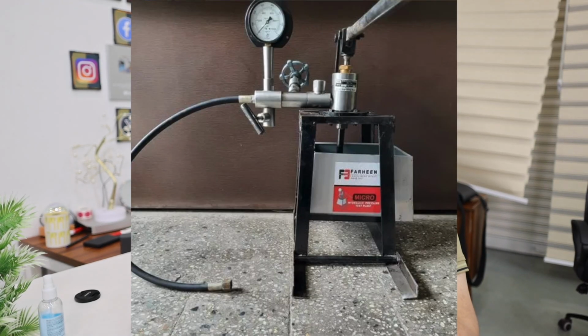Normally it depends upon the consultant requirement. 12 bar, 10 bar, or sometimes we do the testing at 24 bar also. It depends. And after that, of course, we need to fill the water and do the hydraulic pressure testing for 24 hours. Not 2 hours. 2 hours is only for a drama. We need to do the testing for 24 hours. That is safe. Even if you are an engineer and your requirement says 2 hours, go for 24 hours. Face any problem in the beginning, not at the end. That is very, very, very important in the construction industry.